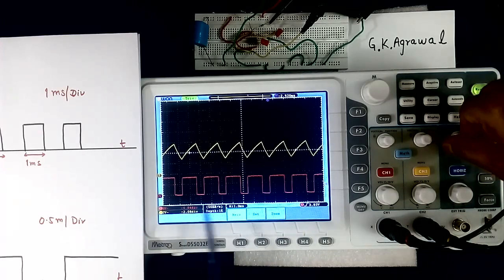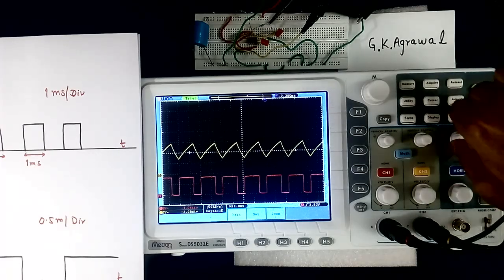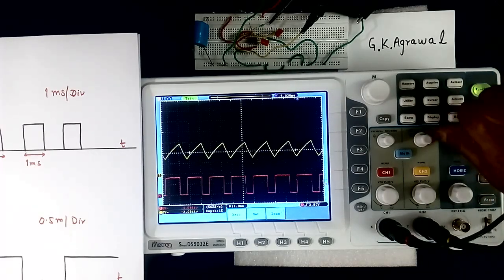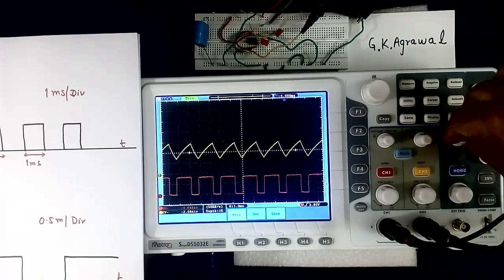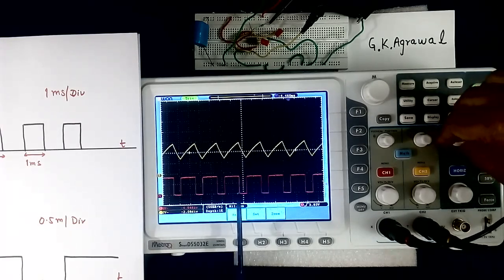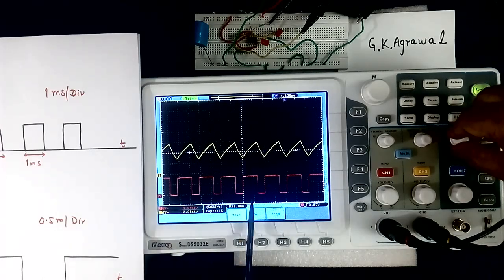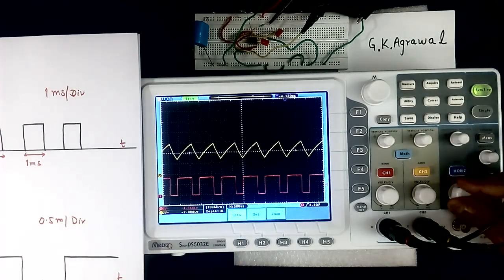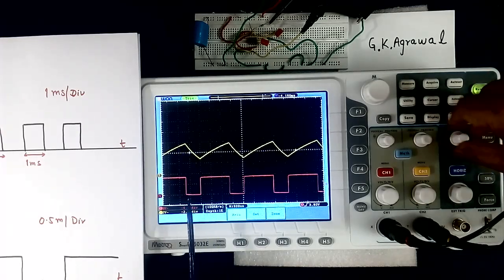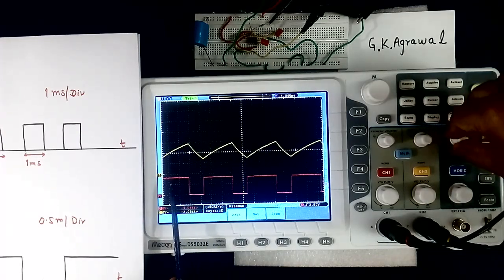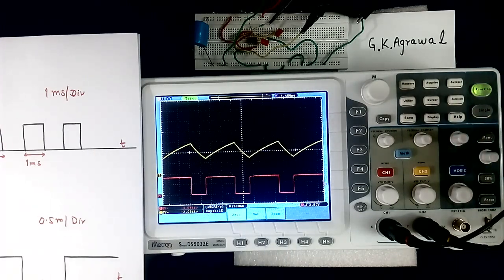This is the wave shape. Using horizontal position control, we can shift this wave shape anywhere. This is used generally to bring the rise or fall edge into the measurement line so that we can measure accurately. Note that this is not triggering control — it is only horizontal position control.